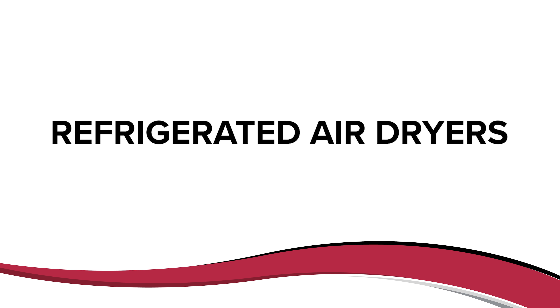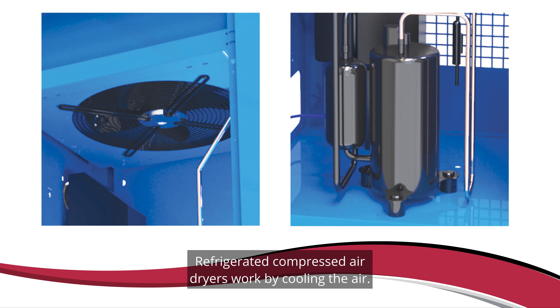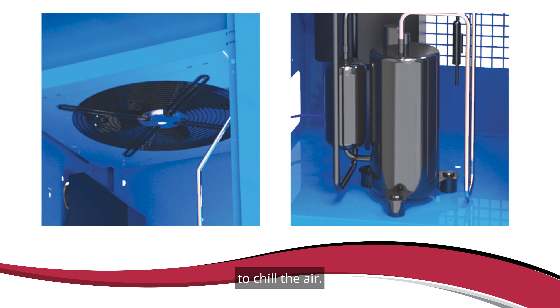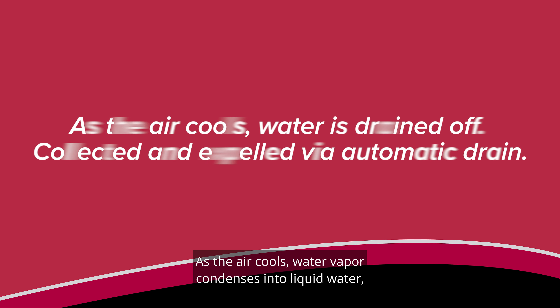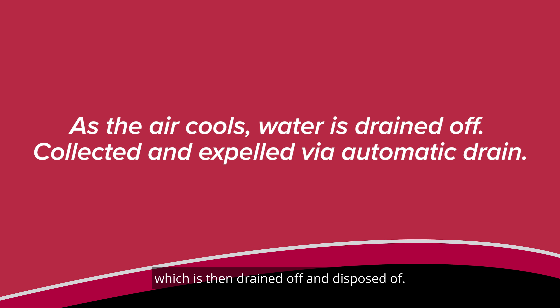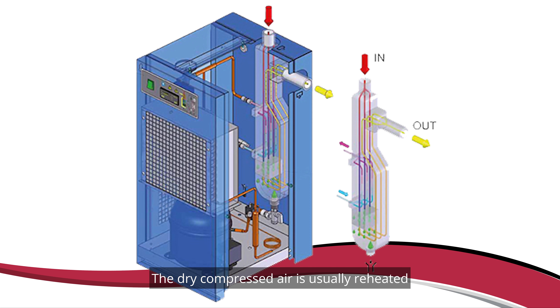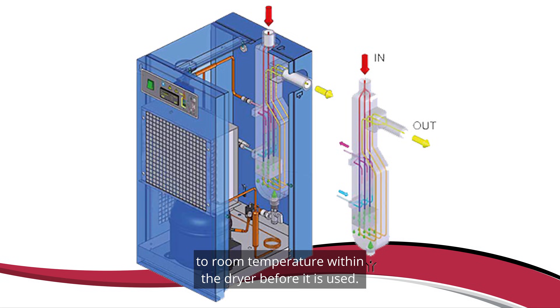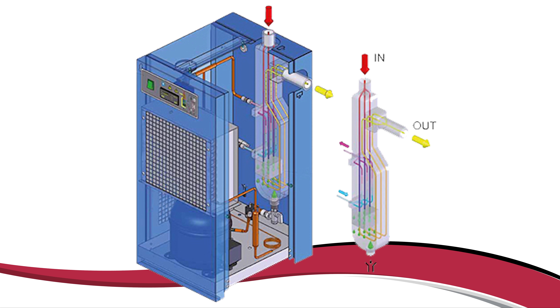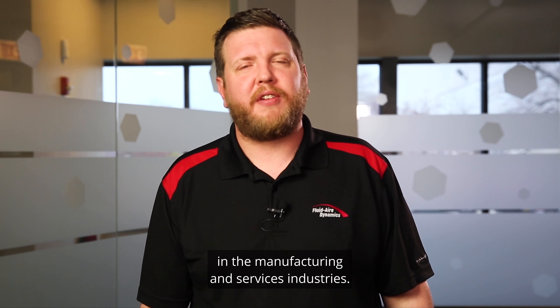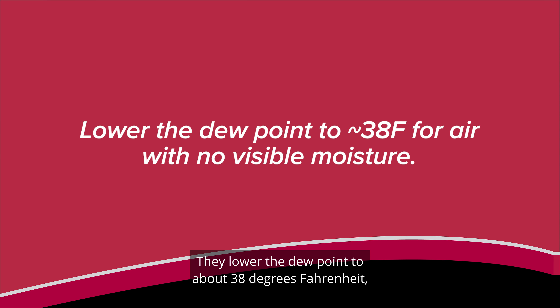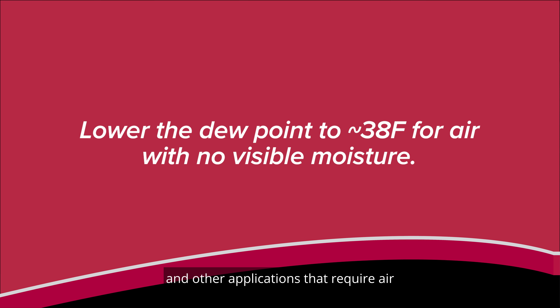Refrigerated air dryers work by cooling the air, much like your refrigerator or freezer, using compressor coils filled with a refrigerant to chill the air. As the air cools, water vapor condenses into liquid water, which is then drained off and disposed of. The liquid is collected in a water trap and expelled via an automatic drain. The dry compressed air is usually reheated to room temperature within the dryer before it is used. Refrigerated dryers are the most commonly used air dryers in the manufacturing and services industries. They lower the dew point to about 38 degrees Fahrenheit.